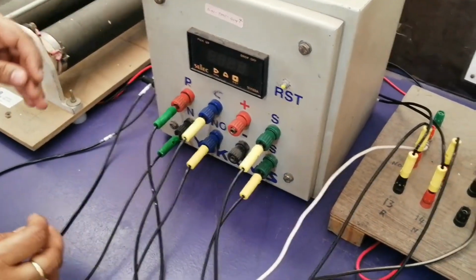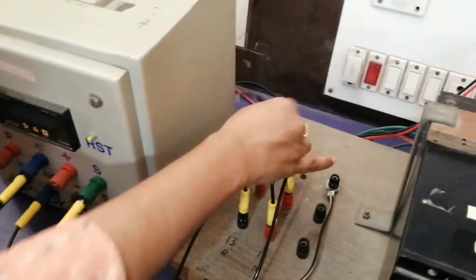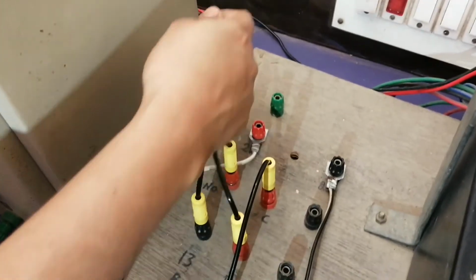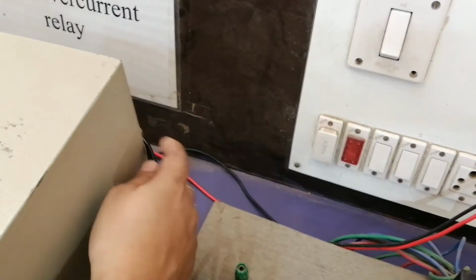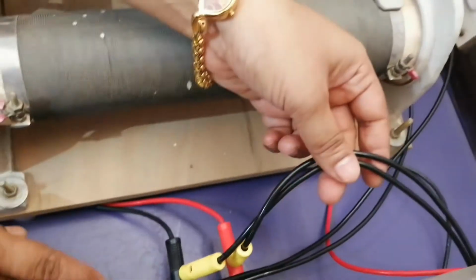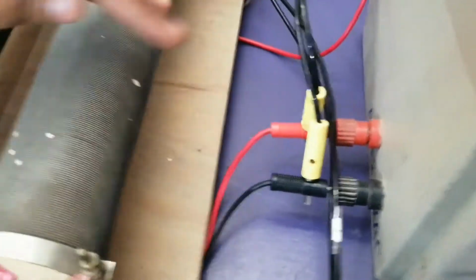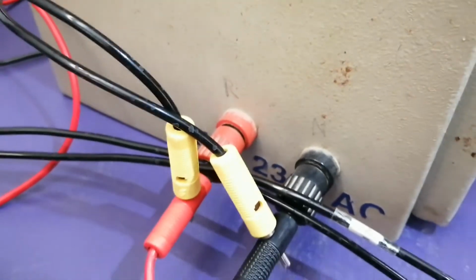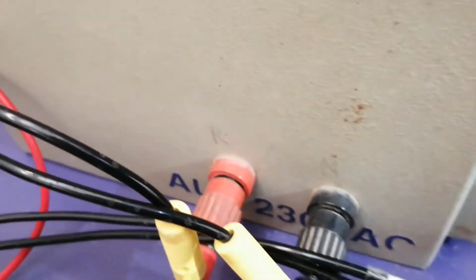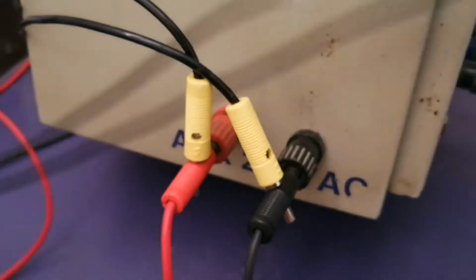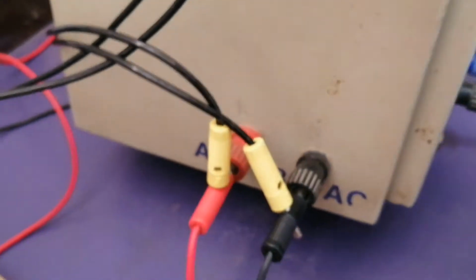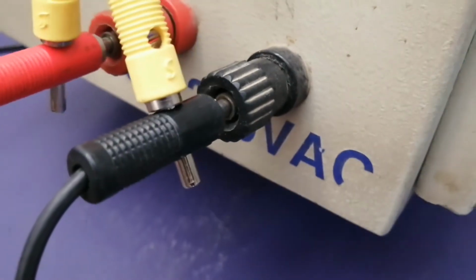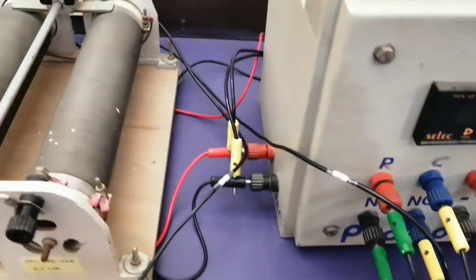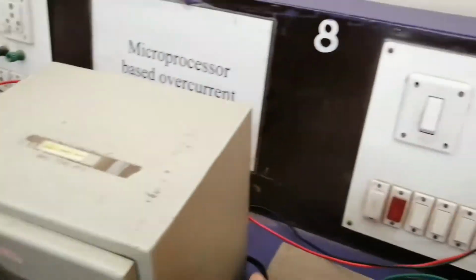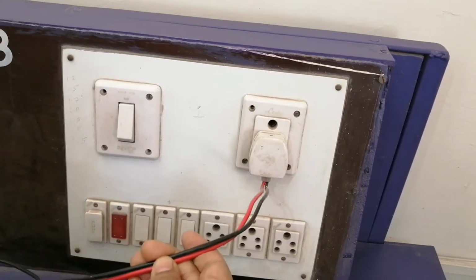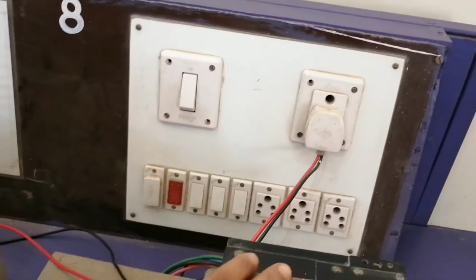Next, let us come to the auxiliary supply. Auxiliary supply is connected to 13-14 of the relay. You can see the circuit diagram. 13-14 of the relay is connected to the timer auxiliary supply. You can see here the name auxiliary supply 230 volts AC. Now see the connection. The auxiliary 230 volts is given to 13-14 of the relay, and that is given through a separate switch, S1. This is the main connection which you have to remember.